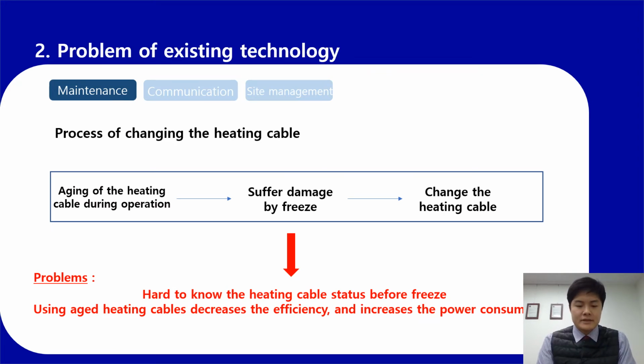As explained, decreased output due to circuit aging can cause freeze accidents. Existing technology cannot figure out the status of circuit aging. Only after the freeze do people understand that the circuits were aged. So the manager changes the heating cable after the accidents happen.